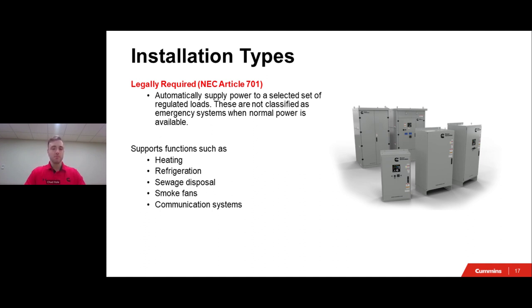power. As with emergency systems, legally required systems are also regulated by municipal, state, federal, and other governmental agencies. The transfer from the normal power source to the emergency power source must be complete within 60 seconds and meet the requirements of Article 701 of the National Electric Code, once again, otherwise known as NFPA 70. And then the same situation applies with your OCPDs. They must be selectively coordinated with all supply side overcurrent protective devices.